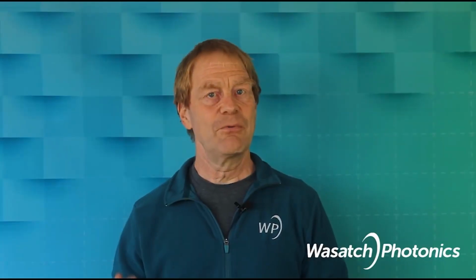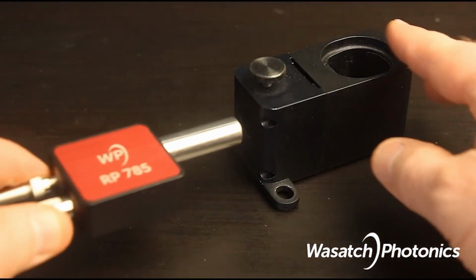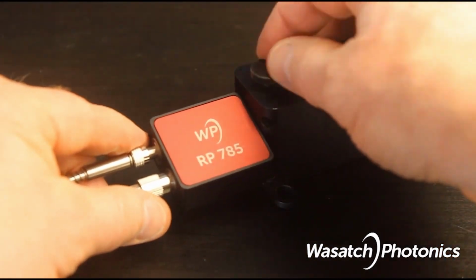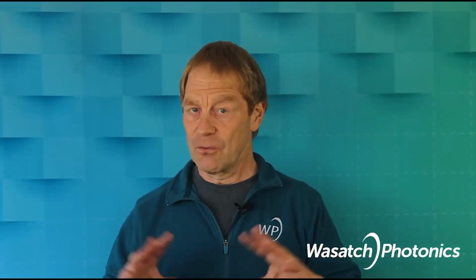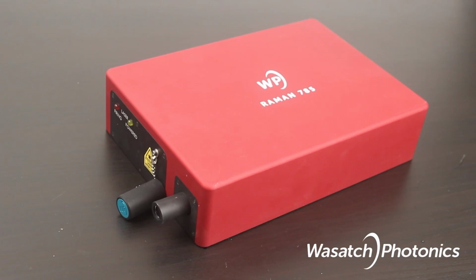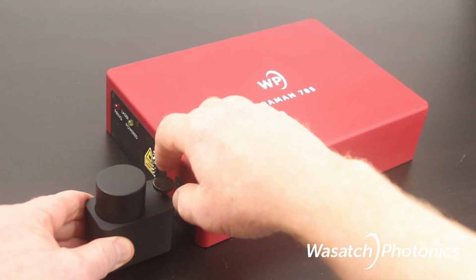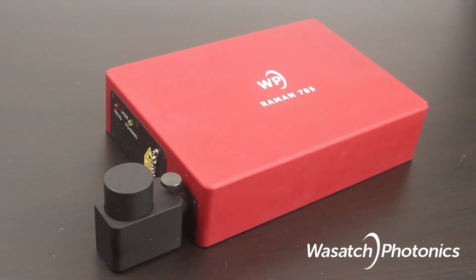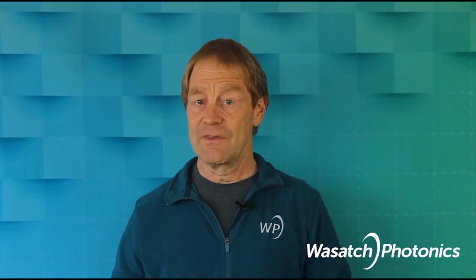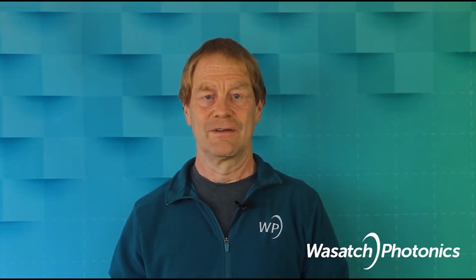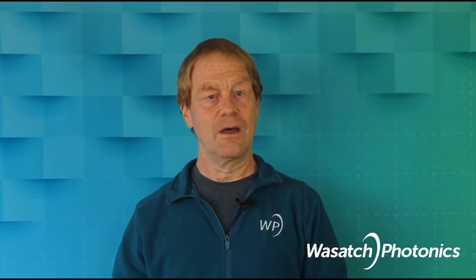Finally, we insert the Raman probe into the sample holder. Push the probe all the way into the sample holder and lightly tighten the thumb screw. For the fully integrated systems, you need to push the sample holder over the front lens of the spectrometer and lightly tighten again the thumb screw. That was it for the optical side of things. So let's turn to the software on the computer.